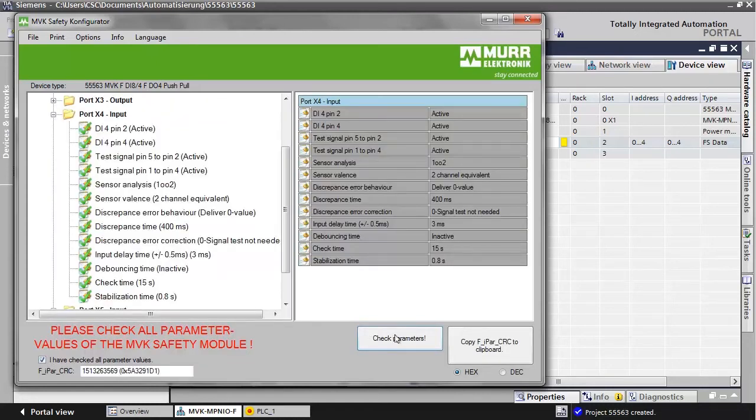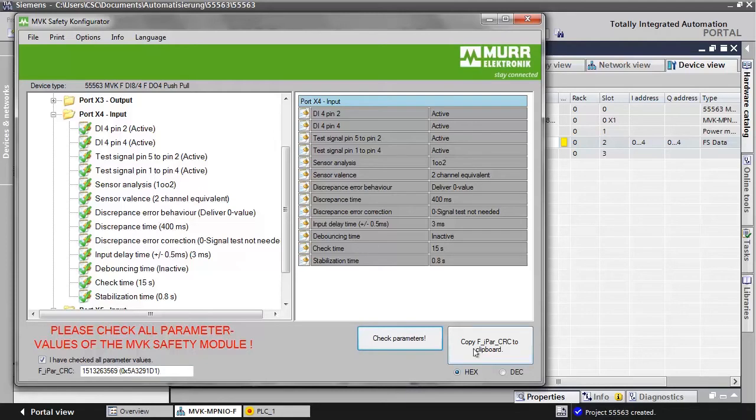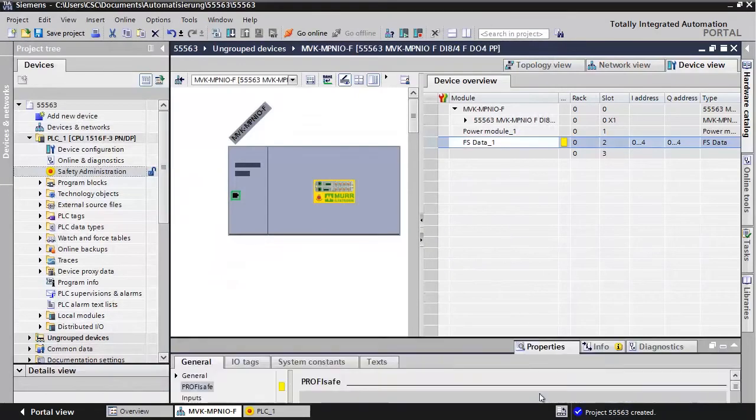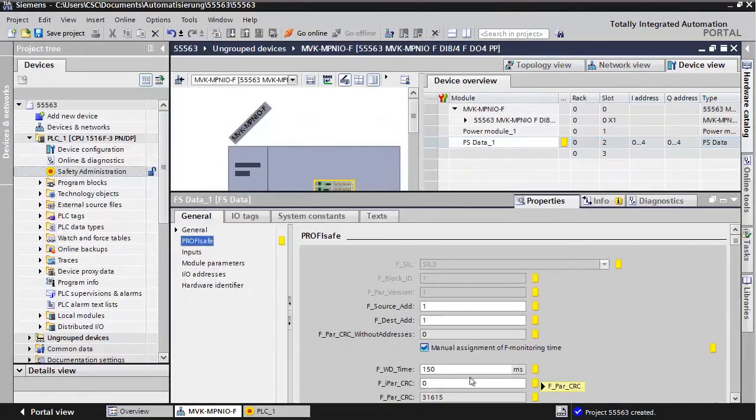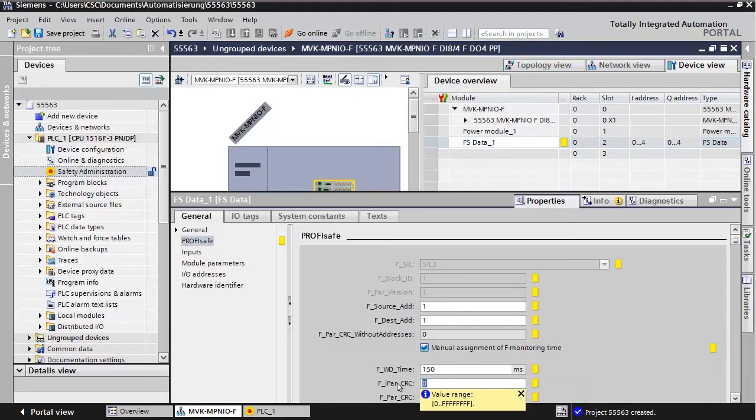Now, we generated the CRC value for the MVK safety module. You can copy it to the clipboard using Copy CRC value to clipboard. Go back to the FS Data module and to the PROFISAFE register. Then, paste the CRC value that was generated before.